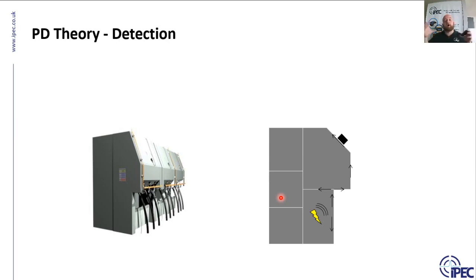The PD travels in all directions away from the PD source, and actually on TEV, the TEV signal, so the cable, like I said, travels about 4 or 5 kilometers. The TEV signal is a much higher frequency signal because we're a bit closer to the PD. So the TEV signal will typically travel about 4 or 5 meters, after which it will attenuate down to 0.